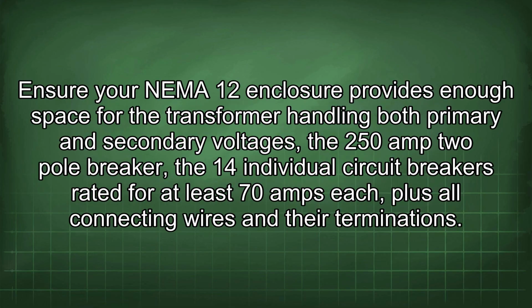Ensure your NEMA 12 enclosure provides enough space for the transformer handling both primary and secondary voltages, the 250 amp 2-pole breaker, the 14 individual circuit breakers rated for at least 70 amps each, plus all connecting wires and their terminations.